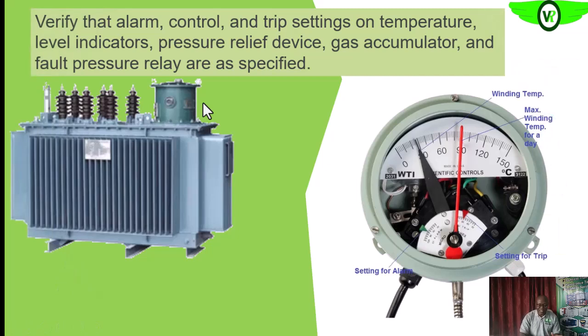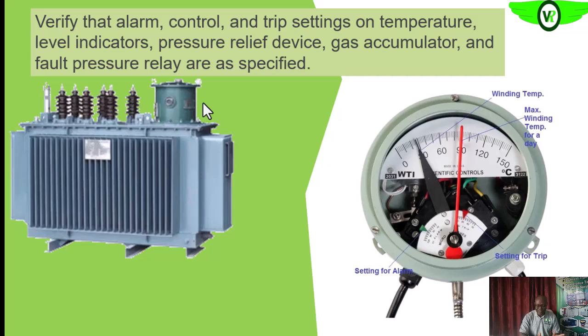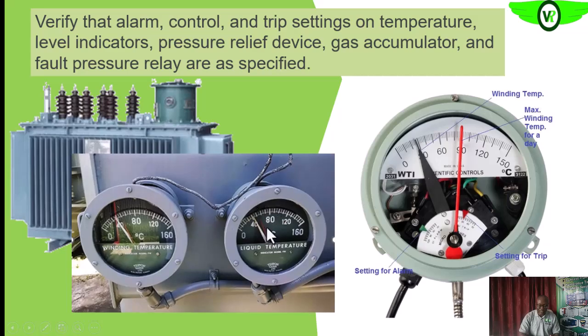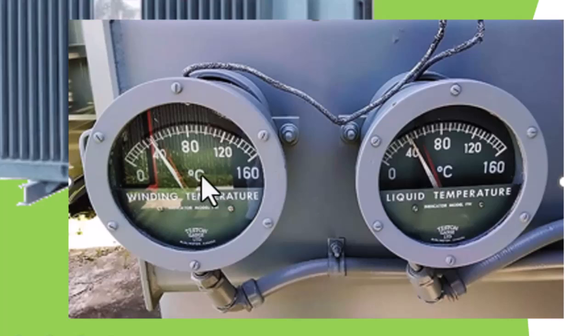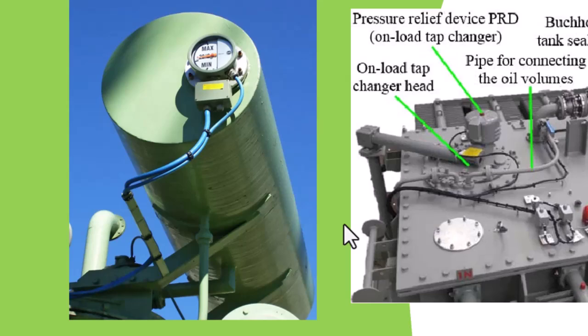So those indicating devices like the temperature and the level, pressure indicating devices, okay, we want to check them to see that the range of the readings match the range that we are expecting in our facility, and also the settings, okay, the alarm settings and the trip settings, they actually match what is specified. Are we getting it? We want to be sure that they are specified for the operations of that particular transformer in our facility. So you look at it and then ascertain that this unit will actually give us the alarm or will actually cause the tripping that we need when the condition of operation goes beyond that level. So that is very important also.